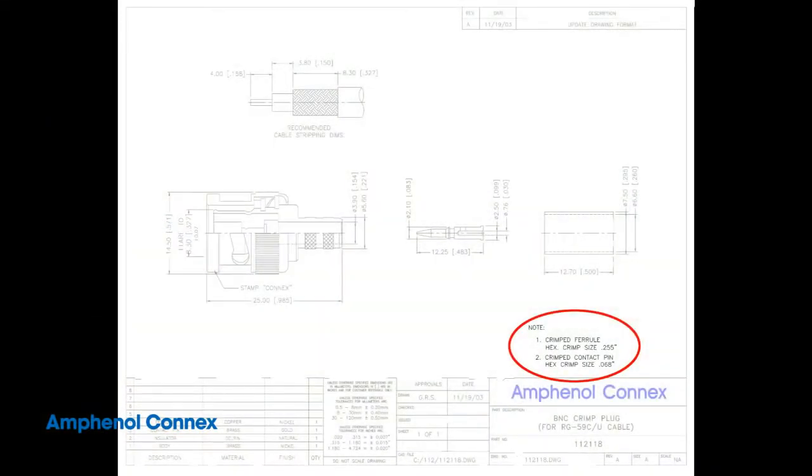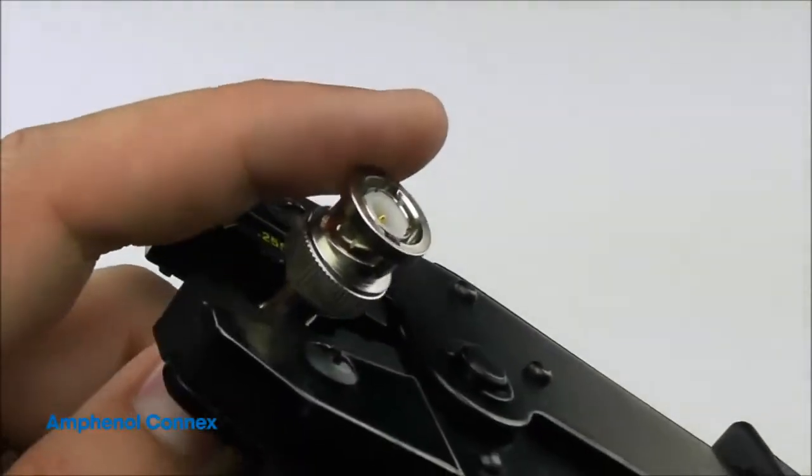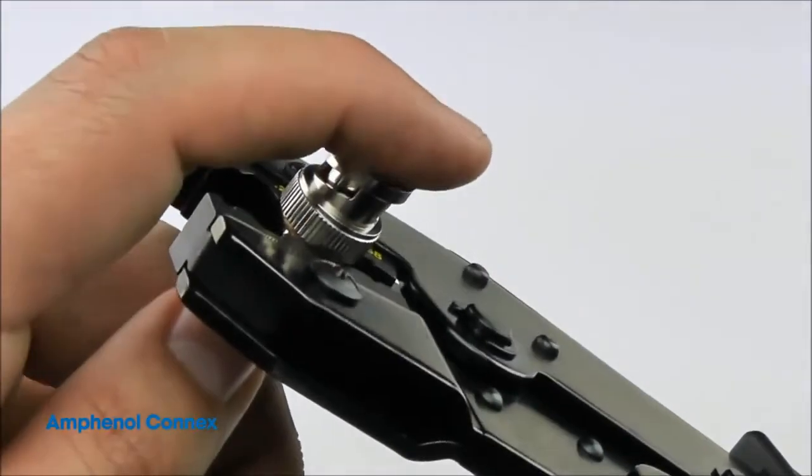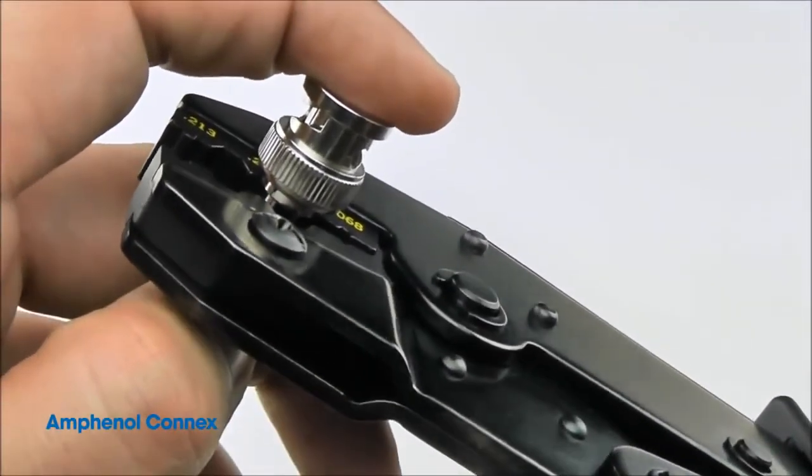Next you will revisit the crimp dimensions on the drawing and note that the ferrule crimp dimension is 0.255 inches. Now, place the ferrule into the 0.255 inch cavity on the jaws of the tool, making sure that the base of the connector body is flush against the tool.